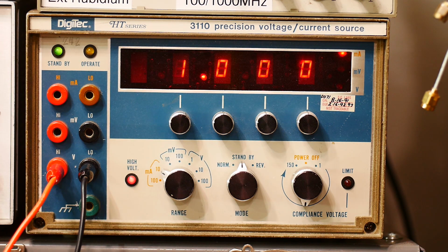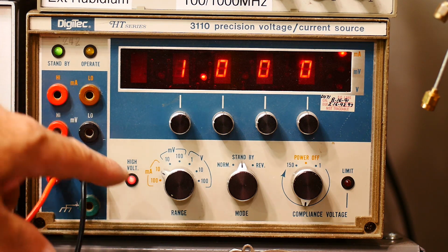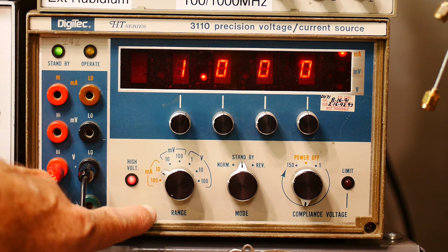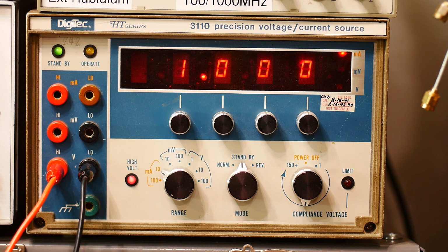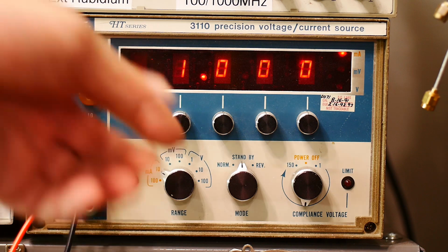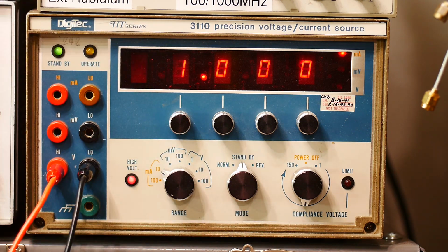And then way over here, it may be hard to read for you because it's kind of in orange, there's the top connector here, which is milliamp. So it has a 10 milliamp range and a 100 milliamp range. And then a little LED comes on here, says high voltage. So that's what this knob is for. It's the compliance voltage for the current source, and that goes up to 150 volts. So it has a very high current compliance.